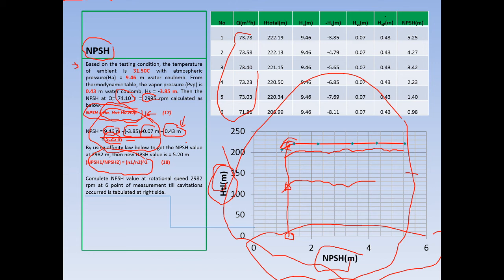Okay, and then you compare how much NPSH available, how much NPSH required. So NPSH available, for example, let's say 3 meters, 3 meters distance from your reservoir below the pump, and the simplified formulation, let environment give you 9.46 meters head, and then 3 meters difference, so you have remaining 6 meters.